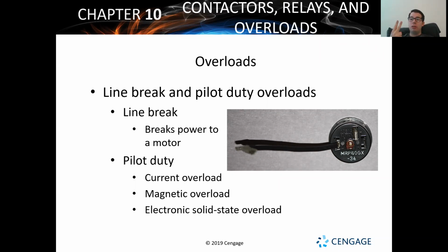We've got two things when we talk about power, especially with contactors. You're going to have a line side where power comes in from your power line. It comes in, goes to the breaker panel. From the breaker panel in the house, it goes out to the outdoor unit. And then from the outdoor unit, it goes right into the bottom of that contactor. That's your line power. The other side of that is your load power. The load power is going out to your loads, to your compressor, to your condenser fan motor, to your blower motor, whatever it might be.